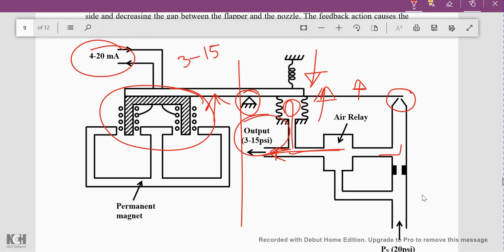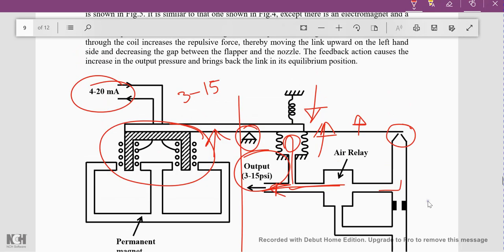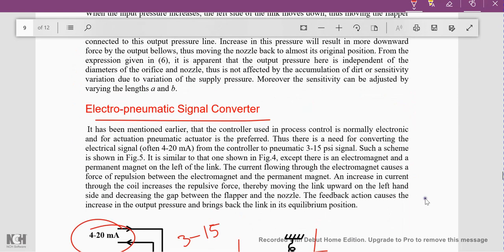This is how electronic control controls the actuator — with a simple current signal and an electromagnet, control of the actuator is obtained. The 4 to 20 milliampere signal is provided by the electronic controller. As stated earlier, the controller used in process control is usually electronic and pneumatic actuator actuation is preferred. Thus there is a need to convert the electrical signal — typically 4 to 20 mA — to a pneumatic signal of 3 to 15 psi.